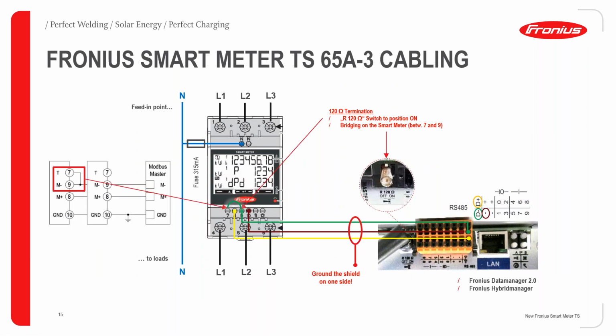And if you look into this Snap Inverter series, this is how it works. In the bottom right corner, you can see the data manager picture from the Snap Inverters. There will be only one orange plug, and on the top right side, you can see the markings D plus and D minus. So these are the Modbus connections in the Snap Inverter series. But otherwise, it's the same as the Gen 24. You don't have to do anything special, except there is the resistor. If you are wondering where the terminal resistor is in the data manager, behind the antenna connection point, you can see the tiny white switch. You have to enable this in the on position in order to turn on the terminal resistance. And it's the same for the Fronius hybrid manager. So if you are using a Fronius Symo Hybrid, it's the same.